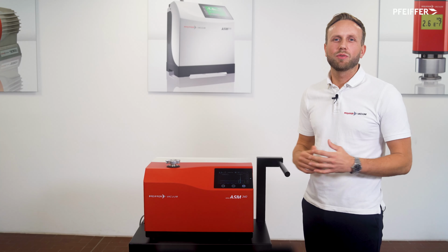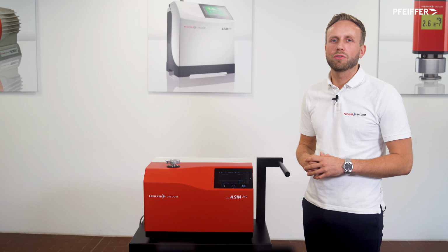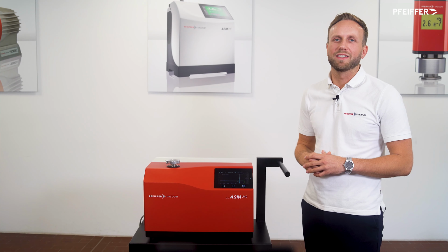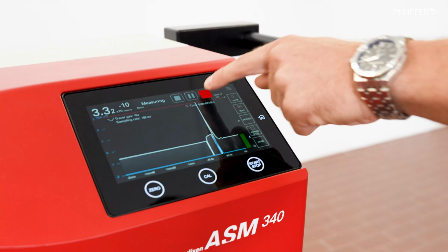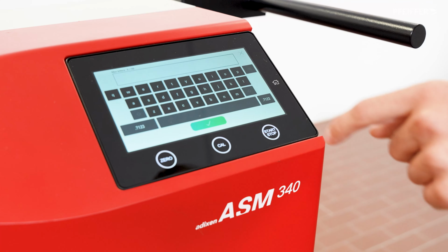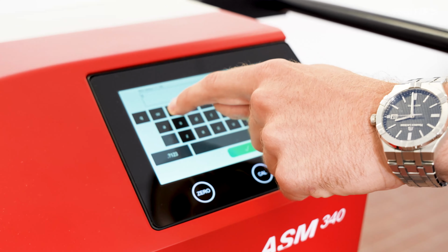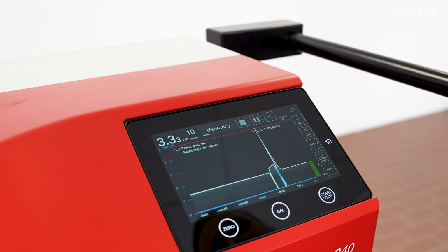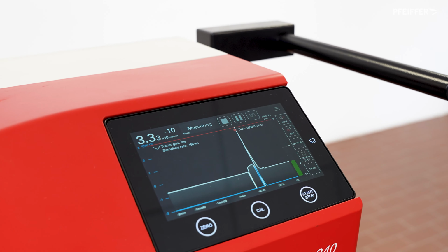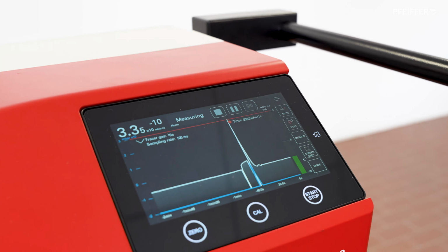An additional feature of the leak detector is to set an individual point in your measurement. For this, you can use the comment function, which helps you to keep a better overview of your recorded data. In this example here, we can set a comment using this button and select, as an example, a test point which we add to our curve. This helps us to keep a better overview and gain some insight on our recordings.